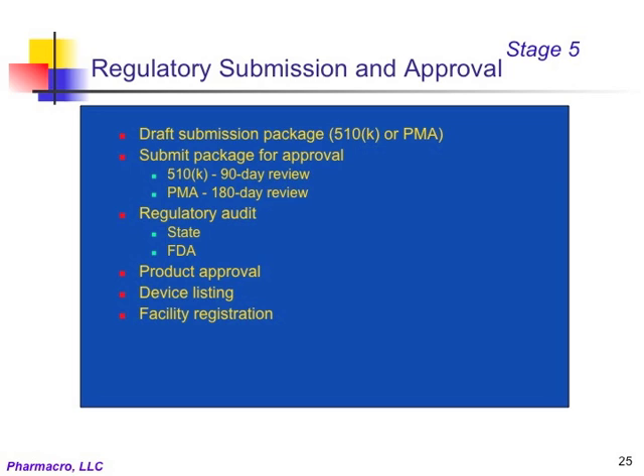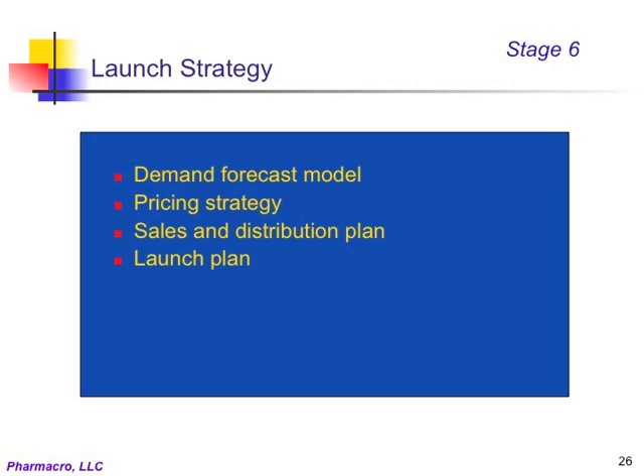The standard period for review by FDA for a 510(k) application is 90 days, and it is 180 days for a PMA application. These time periods for review may be extended depending on how much additional information the FDA may require from the sponsor during the review period. Following product approval, the device is listed in the FDA registry, and the manufacturing facility is also registered with the FDA. The last step in commercialization is the product launch.